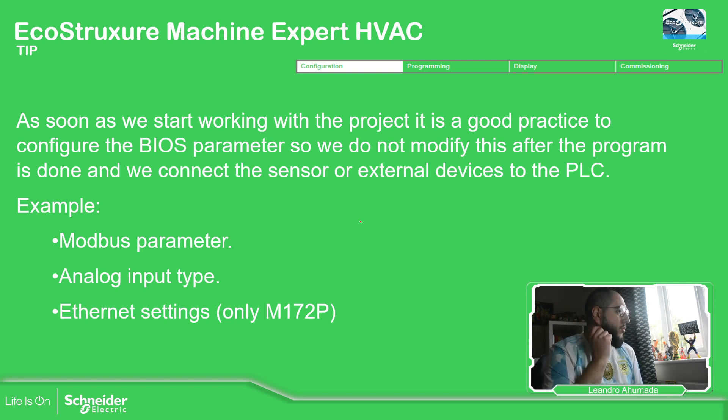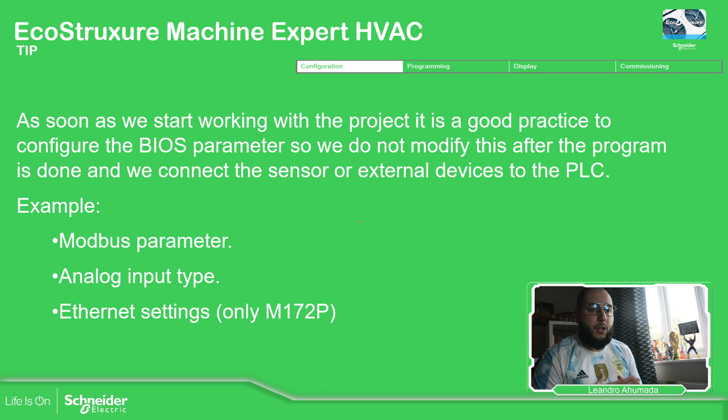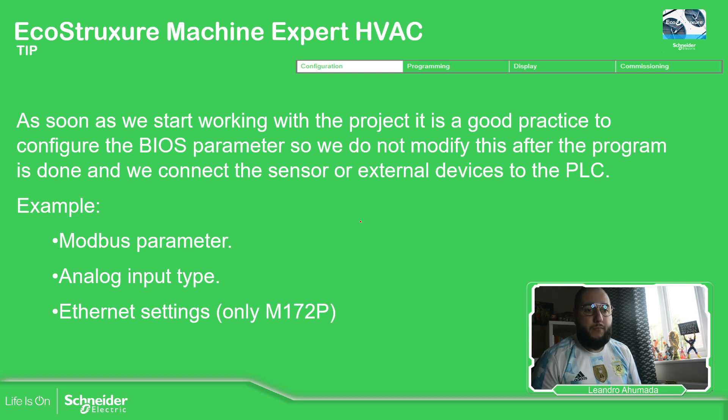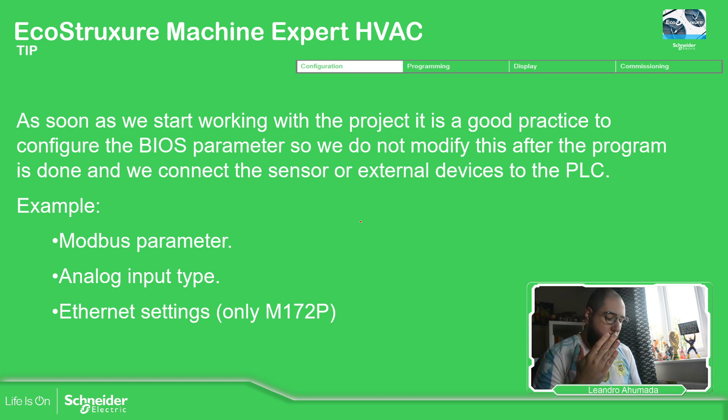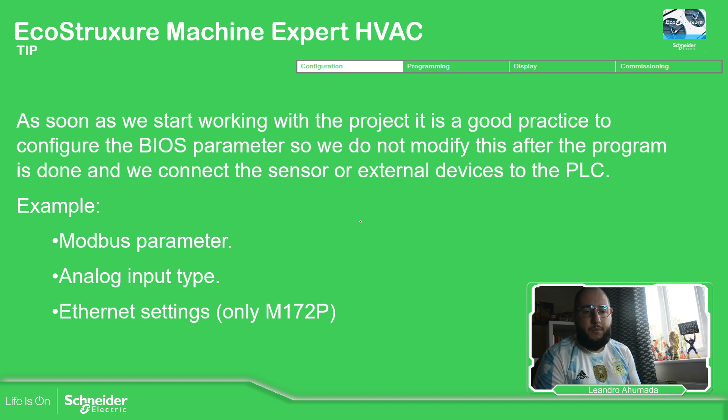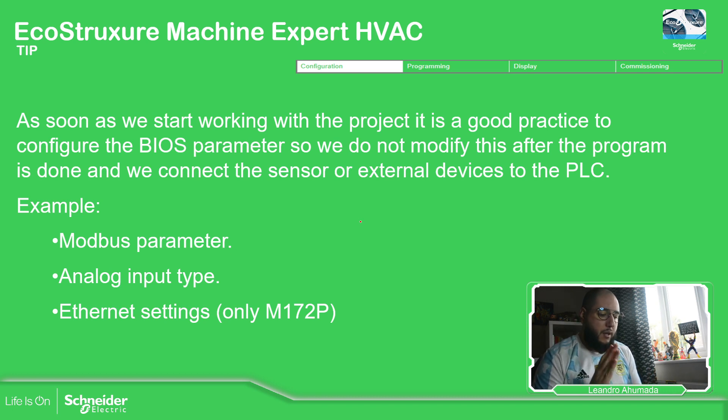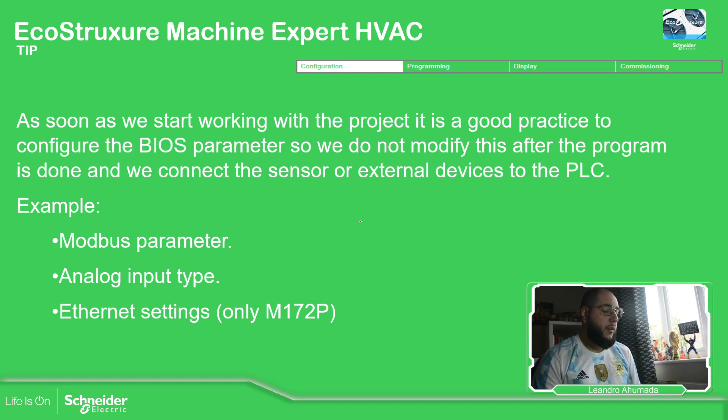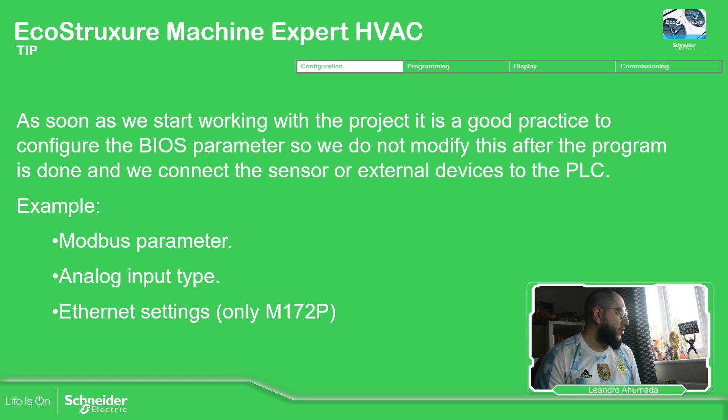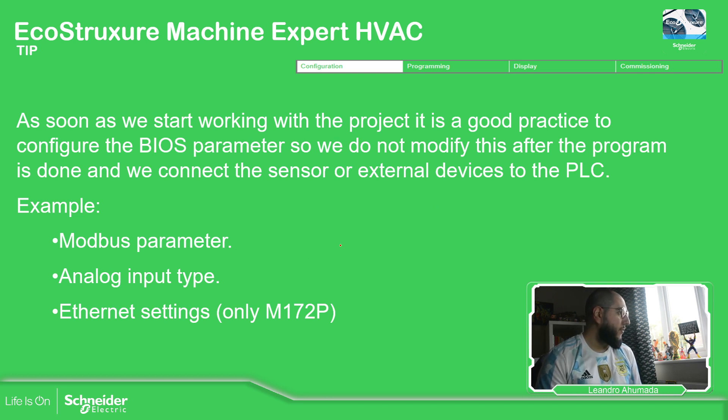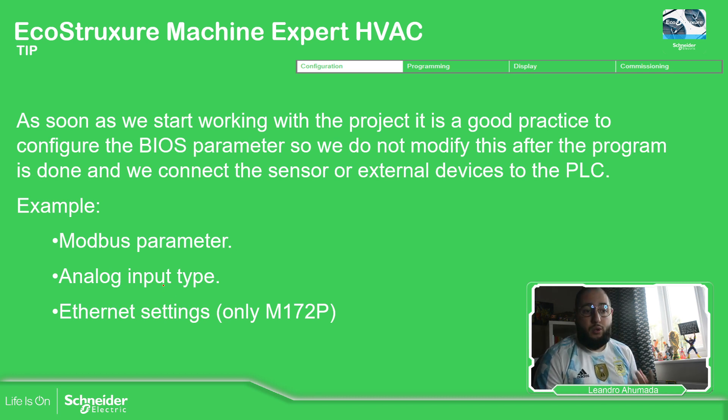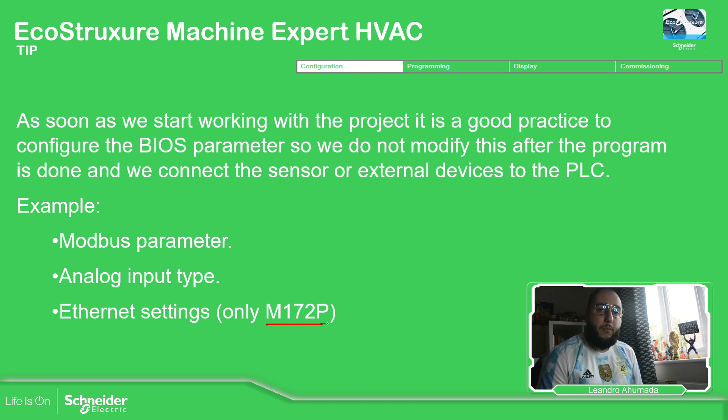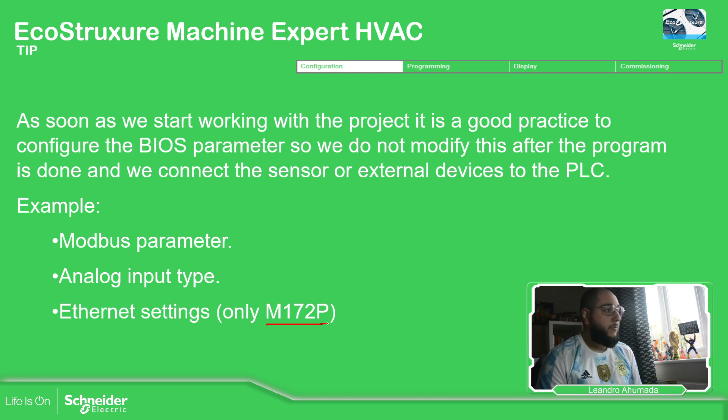Now, this is something very important because sometimes we just made a modification or we don't do any modification and we don't know what happened. So it's important to, as soon as we got the PLC, or we got the project that we're going to work with, spend some time changing the BIOS parameters so you can have it by default. One of the things that you can always check is the Modbus parameter. If you're going to make communication, the analog inputs that you're going to use in case you're using it and also the Ethernet settings that is only available for the performance. The M172 optimized doesn't have that option.